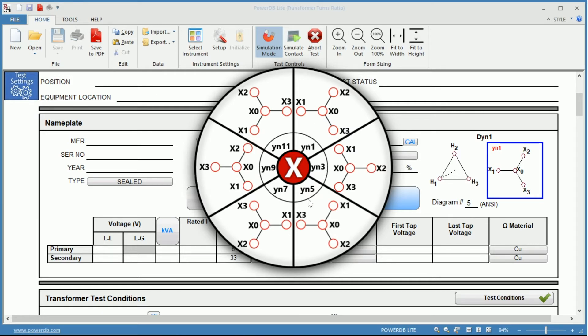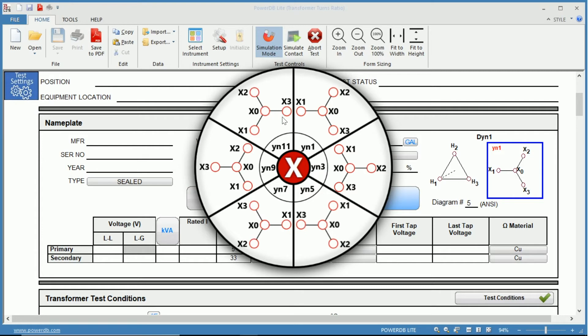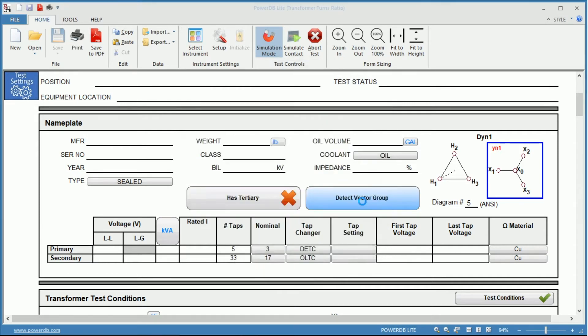If we click Y with a neutral we can see we have six options to choose from: the yn1, 3, 5, 7, 9, and 11. So you know you have a Y with a neutral but you don't know which of these six diagrams corresponds to the transformer that you're testing. And that's where the detect vector group comes in.